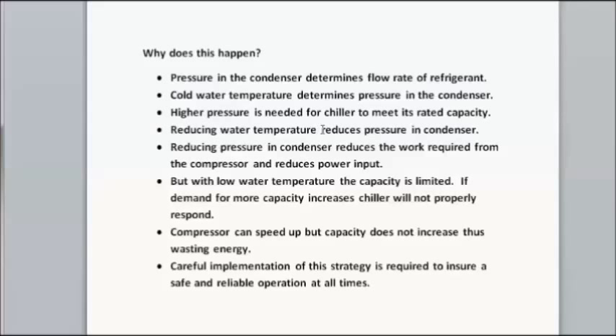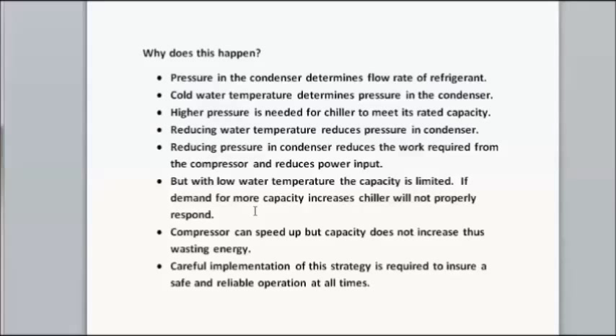But when you reduce the water temperature this reduces the gas pressure in the condenser and that reduces the work required for the compressor and reduces its power input. With a low water temperature your capacity is limited. If demand for more capacity increases at this point the chiller will not respond unless you increase the condenser water temperature. The compressor will try to respond by speeding up but the capacity doesn't increase and you start wasting energy. So the point is that careful implementation of this strategy is required to ensure a safe and reliable operation at all times.